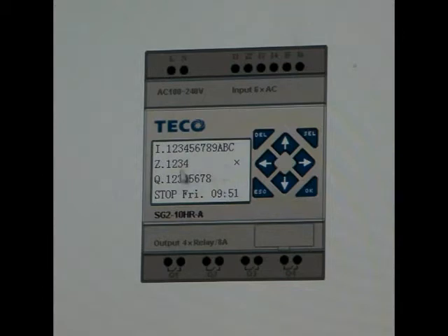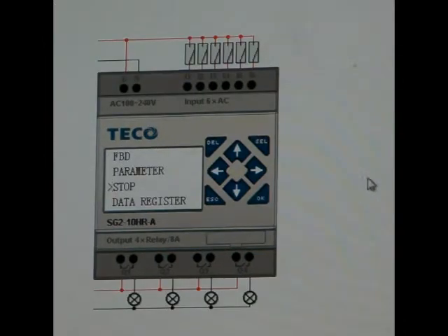To change that from the I/O screen, you just hit escape. You can see when you hit escape, it indexes between the I/O screen and, for the moment, let's call it the stop run screen. Again, I just have to move the arrow key down to run. I want to select that to change it. And I want to say, OK, I want it to run. Then it's going to ask me, are you sure? And I'm going to say, OK. Now it's in the run mode, and you can see that the control is activated.